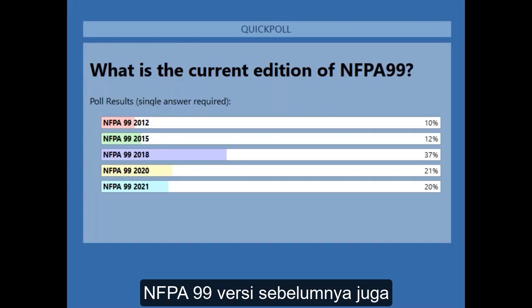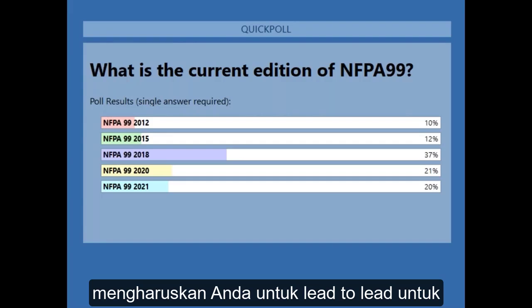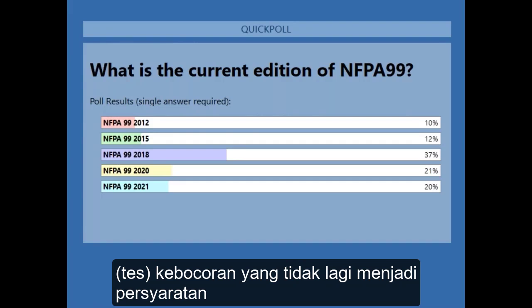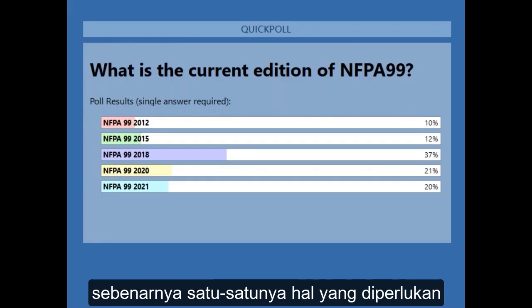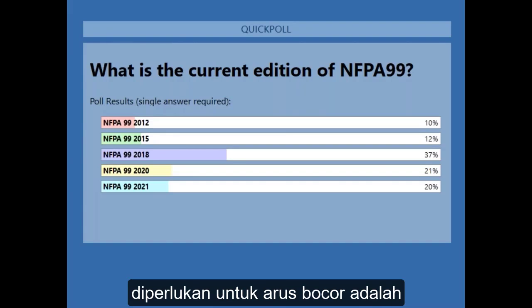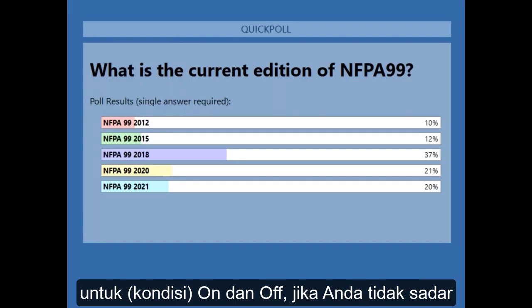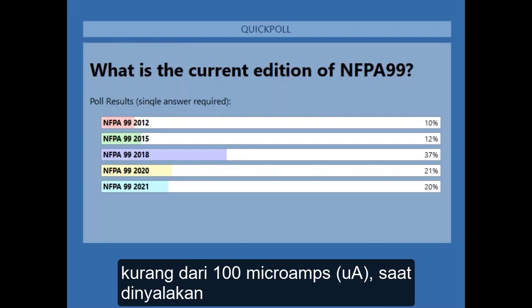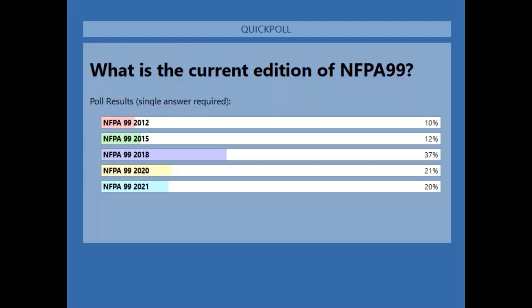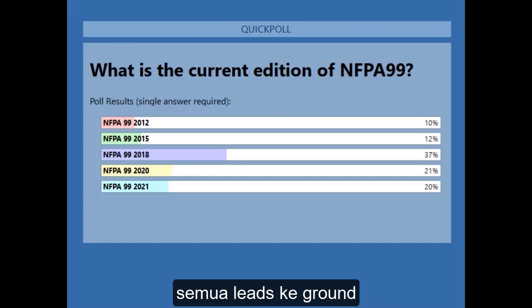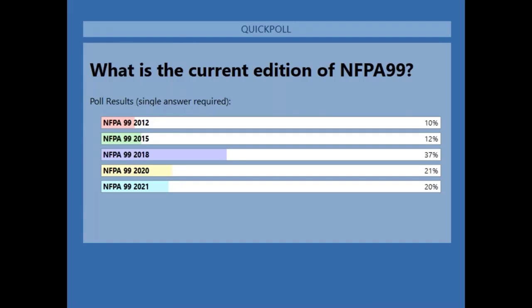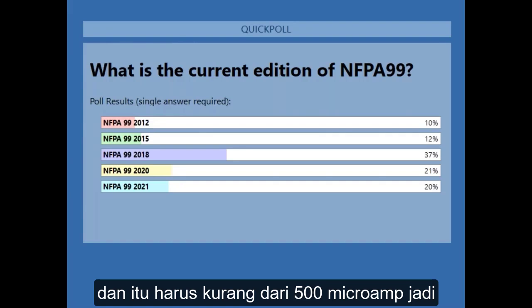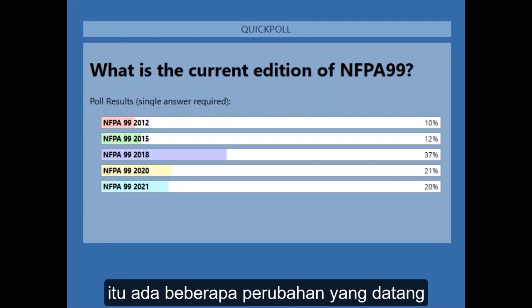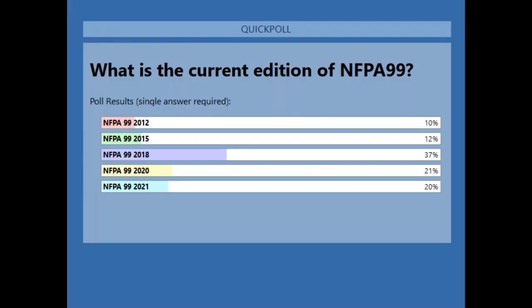The previous versions of NFPA 99 also required you to do lead to lead for leakage. That is no longer a requirement. Really, the only thing that is required for leakage current is your standard leakage current, which has to be on and off. If you're not aware, when a unit is turned off, it has to be less than 100 microamps. When it's turned on, it has to be less than 500. And then all leads to ground has to be less than 500 microamps. So those were some changes that a lot of people are not quite aware of.